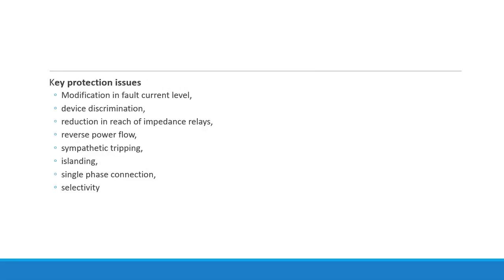So broadly, if we say what the key protection issues are, they include modification in fault currents, that is grid connected and islanded mode, device discrimination, reduction in reach of impedance relays, reverse power flow, bidirectional power flow, which we were talking about, sympathetic tripping, islanding, single phase connection, selectivity. So these are the issues we discussed, summarized here.